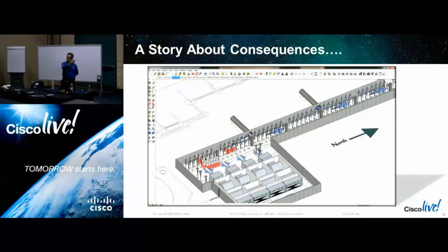So that stream of air was either picking the stuff off of the tanks and bringing it into the data hall, or in other conditions, it was letting it grow. It turned out that because of the various factors, there happened to be a sweet spot for the contamination in the data hall on the southwest side, and that was where the failures all occurred.